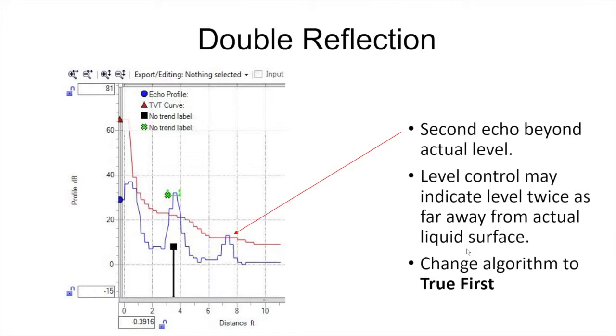Generally the second echo would be the only one to worry about, but if the second echo is in some cases stronger than the first echo, the true echo, then the radar gauge would indicate the level as being twice as far away from the radar sensor face as it actually is. In this case we definitely want to make our algorithm true first so it selects only the first valid echo.